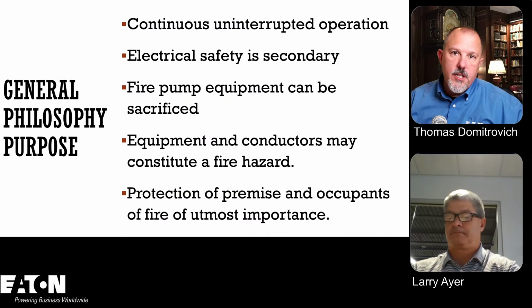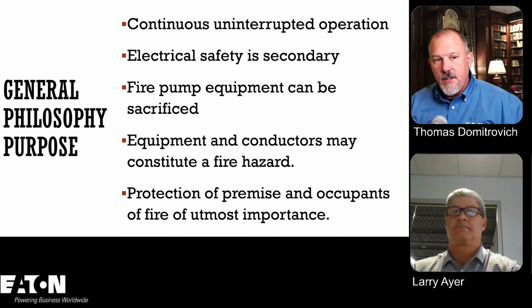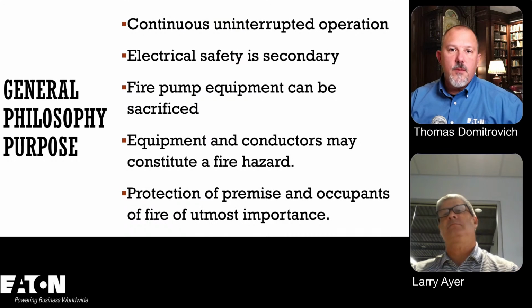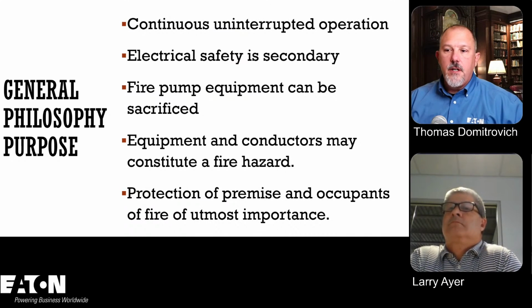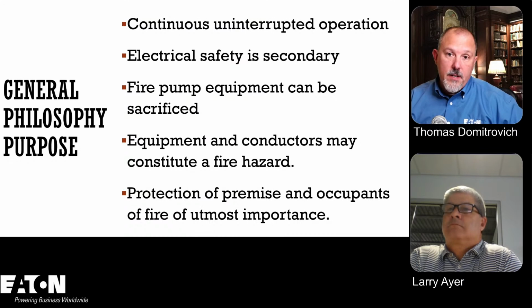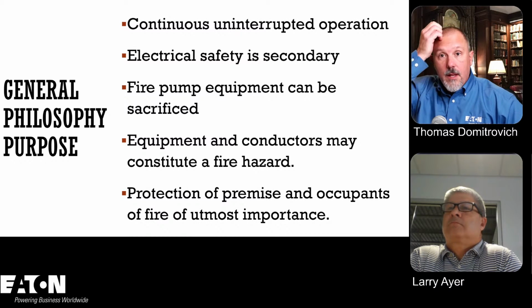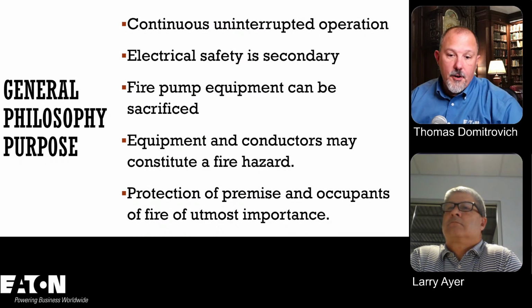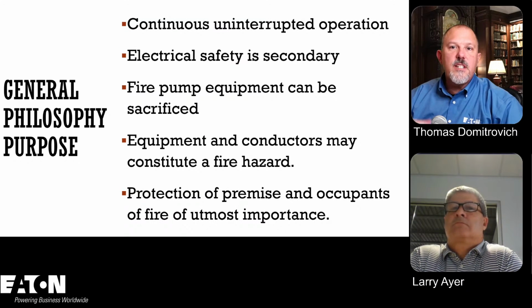They're not so much worried. Now, from a safety perspective, there are provisions, and we'll talk about the protection of the conductors, because you want to keep the fire pump system as simple as possible, right? Because simplicity breeds reliability in some cases. Arguably, we could probably debate that topic all day, but you want to keep things simple. So there are things that we do, because you're probably coming right off the service. There are things like fire ratings, which we'll talk about. There are special precautions you have to take with regard to those conductors.